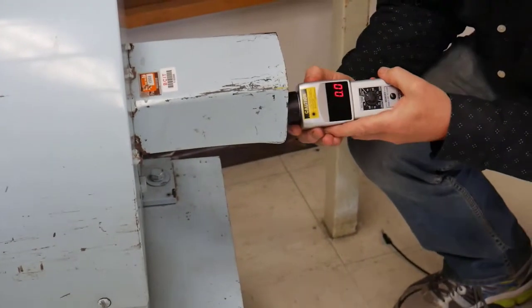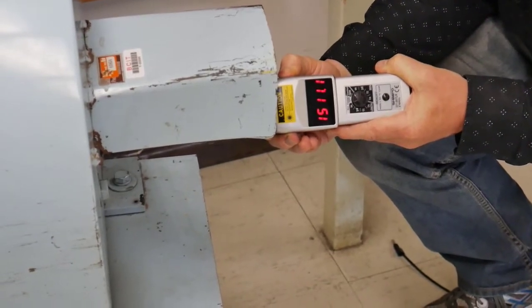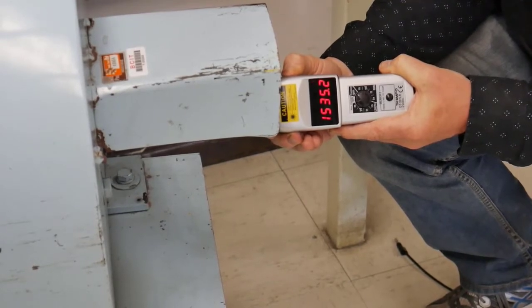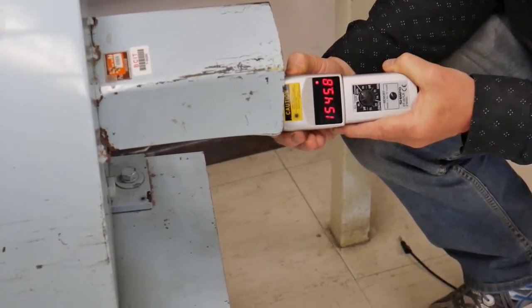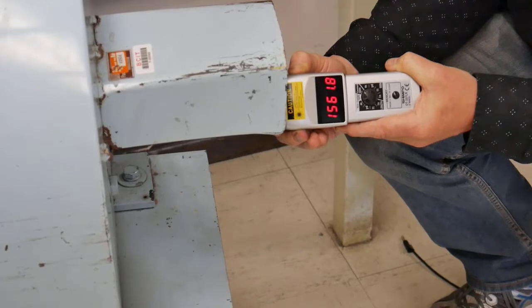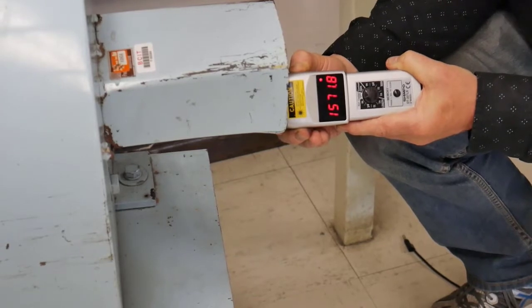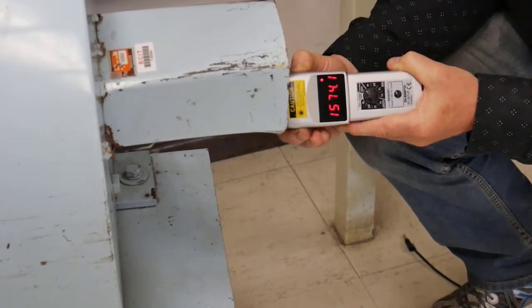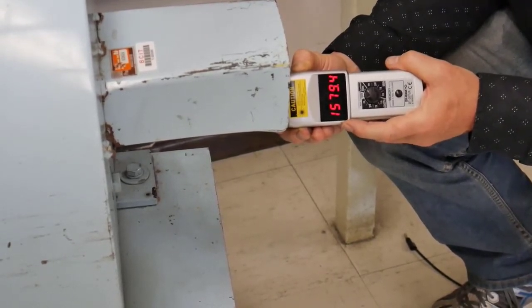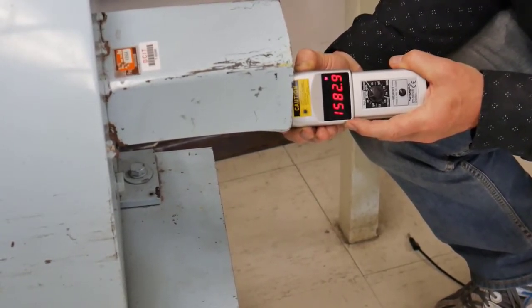Let's look at our speed. We're not quite at full speed for this resistance yet. We had high enough torque to start the motor, but as it accelerates, this is the maximum RPM we can get with the existing resistance in the rotor circuit. We can't produce enough torque to keep going faster right now.